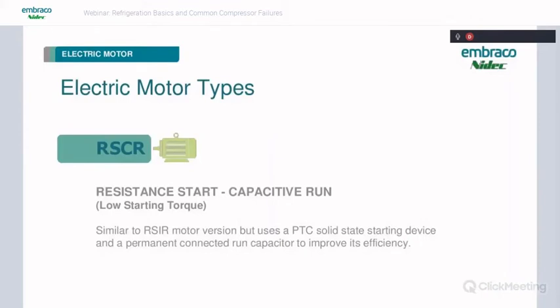Then we have the RSCR, so it's resistive start, so no start capacitor, but capacitive run. So we have an added run capacitor. And basically what we're doing, this motor is still low starting torque, but it has an added run capacitor giving it a higher running torque. So basically what they're doing here is they're giving that motor higher running efficiency. So you see this motor, this is probably one of the more common motors you'll see in residential refrigerators now because of that added efficiency of the run capacitor.